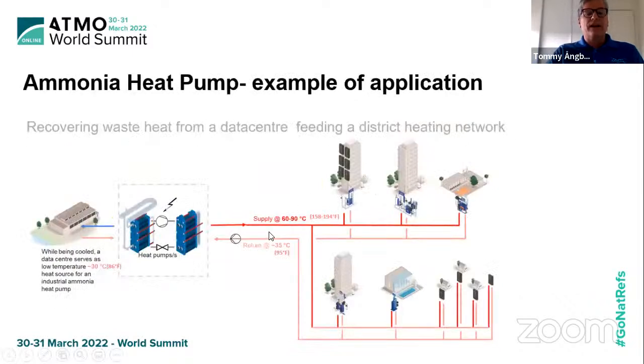One example of an ammonia heat pump that we have supplied is an application, we can go into detail later, to recover waste heat from a data center to feed a district heating network with heat. There are a lot of data centers built around the world, and they need to be cooled. And why waste that out to the atmosphere? Use the heat, take it into a heat pump, and produce higher temperatures that are perfect for other purposes, in this case, for district heating.